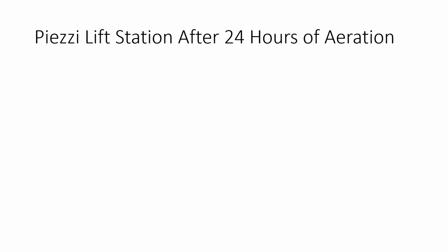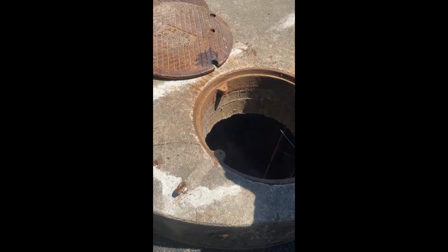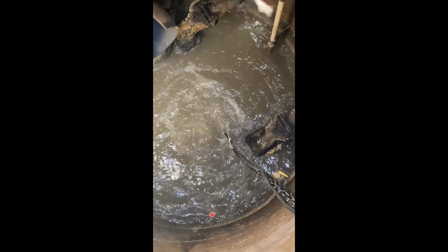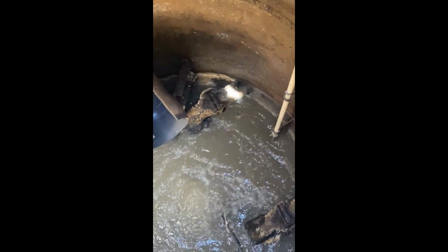Here we'll have that same lift station, Piazzi Lift Station, after 24 hours of continuous aeration. It's been 24 hours that we've been running this. Notice after 24 hours, the grease ring around the edge has been broken down. Looking pretty good.